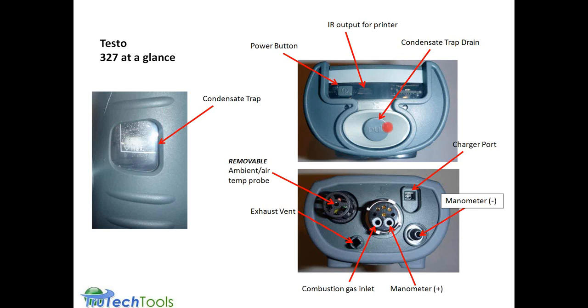The condensate trap, here's a top view of that. The plug says pull on it. That doesn't mean pull out. It means pull slightly out. You pull it out a little bit to allow it to drain. Then you make sure you push it back. It's got a nice little bib along the side, which allows you not to spill condensate back inside the meter. The charger port shown here is keyed. It's got a little lobe on the bottom, so you can never confuse it or put it in backwards or sideways.